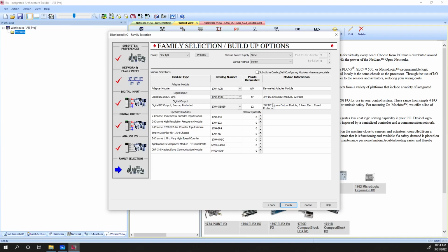So always have extra I/O available to you, whether for future proofing because you might want to add some more sensors and heaters or light bulbs or whatever, or because you're worried about equipment outputs failing. If you're going to have a failure, most likely it's going to be an output. Your inputs are damn near bulletproof. As long as you put the right voltage to your inputs, you'll be fine. Outputs are what you're going to break because something's going to short circuit. Your heater is going to have a short in it, so it's not going to have any resistance, and it's just going to flood current through that contact or whatever the case is. That's what you're going to blow up, most likely.